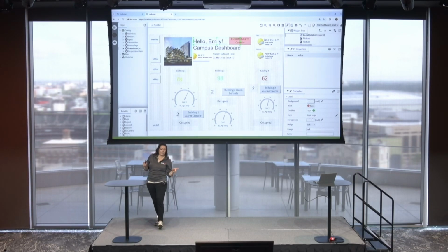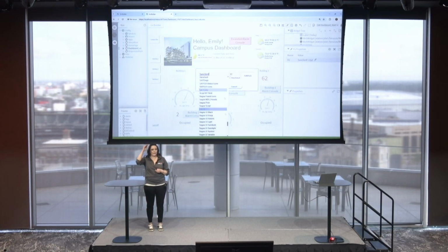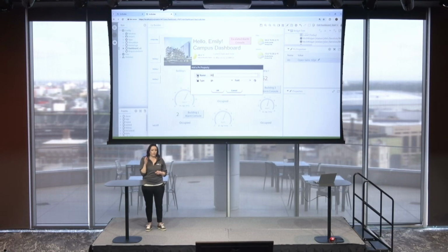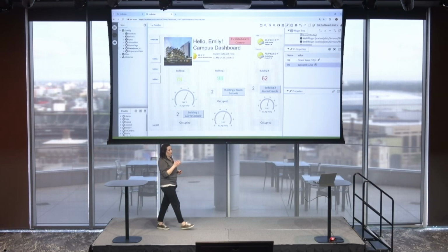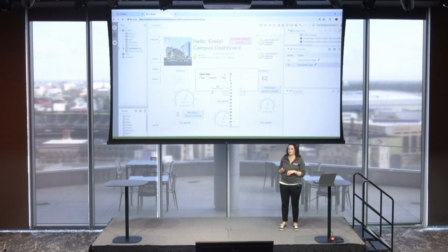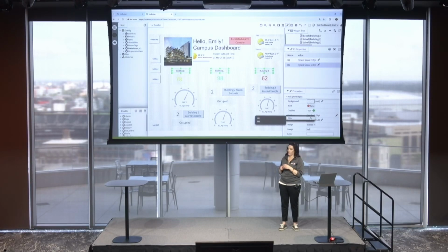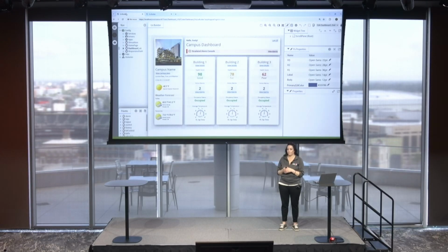However, we're here to talk about consistency, and what tools does Niagara have to help you? Those are PX properties. If you don't use PX properties, you should, because I can go ahead and line up my H1, H2, that's my heading 1, heading 2, and set up what fonts I'm going to apply across the board, so that I can then link those as I'm creating each of these widgets, and keep these consistent throughout the entire page. So as you see here, I'm setting up my headers that I'm gonna put into my PX properties, and then I'll come in and link them into the font. If you didn't know about this, you right click, link, and then bind it to the PX property right here.